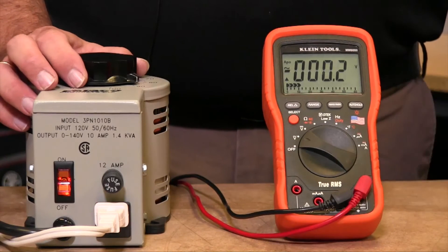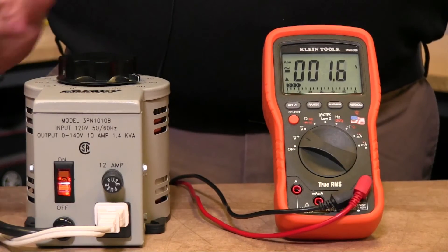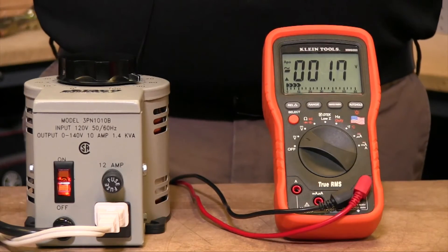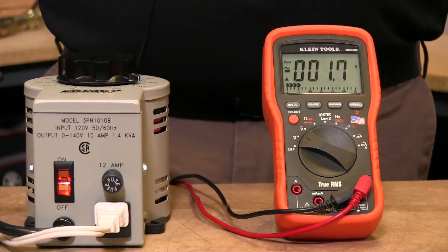now you go to an outlet in your home, and when you plug into that outlet you're measuring something a little under 120. It will show you now the voltage drop that you have in the wire from your circuit breaker panel to that outlet.